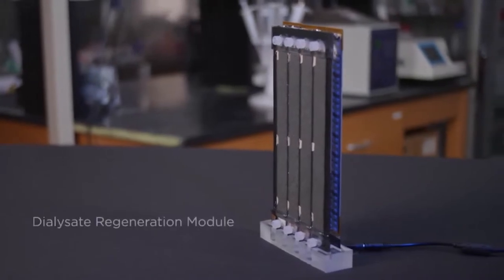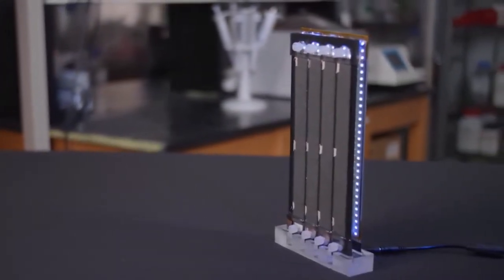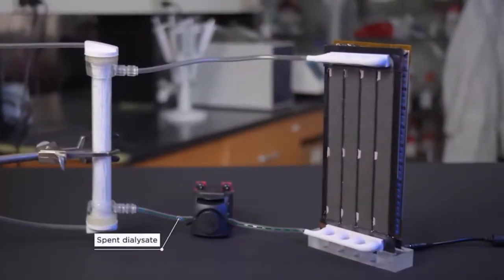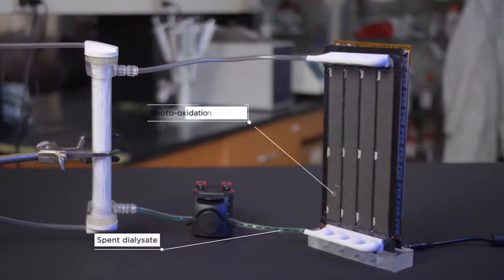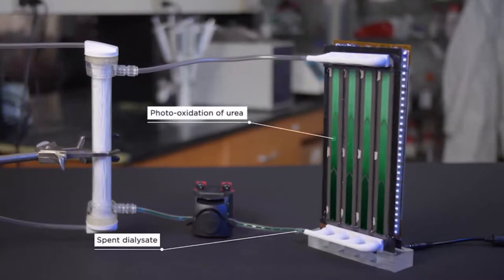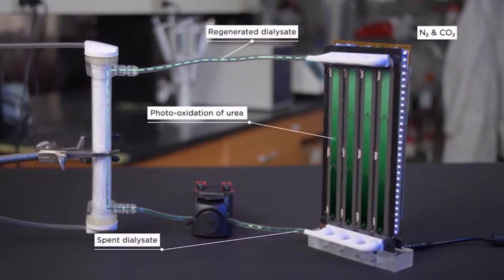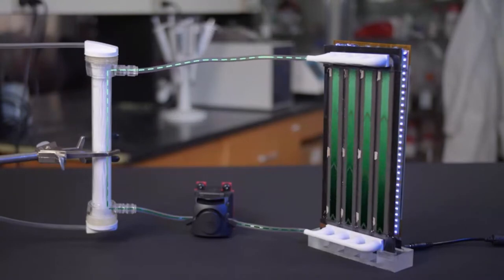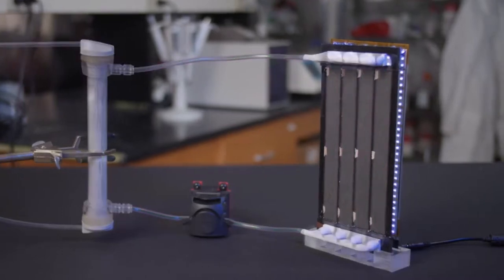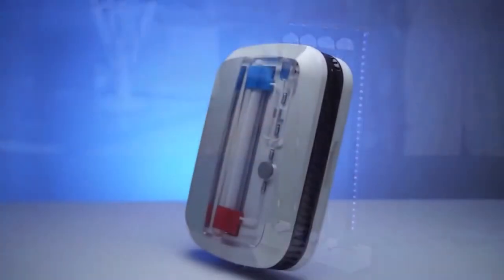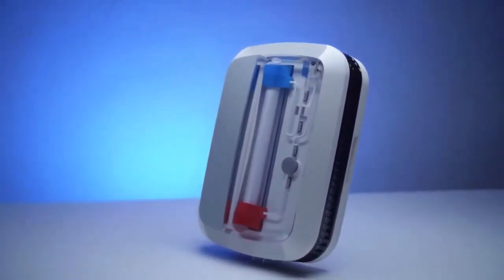The Active is enabled by a dialysate regeneration module. The mechanism of regeneration is based on the CDI's proprietary photooxidation technology. Spent dialysate flows from the dialyzer to the dialysate regeneration module, where urea is decomposed into nitrogen and carbon dioxide by photooxidation. Regenerated dialysate is returned to the dialyzer, and this process repeats. The dialysate regeneration module untethers the Active from an external water supply and enables it to operate with a small, closed-loop volume of dialysate. This revolutionary technology allows the Active device to be smaller, lighter, safe, and effective for renal replacement therapy.